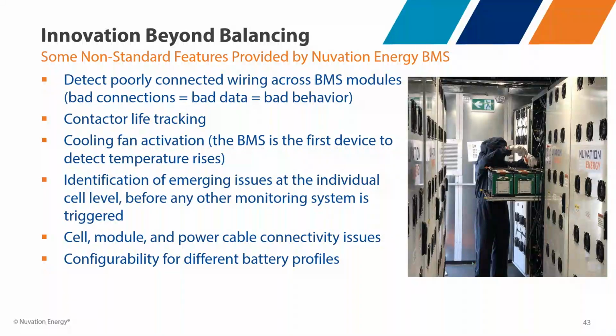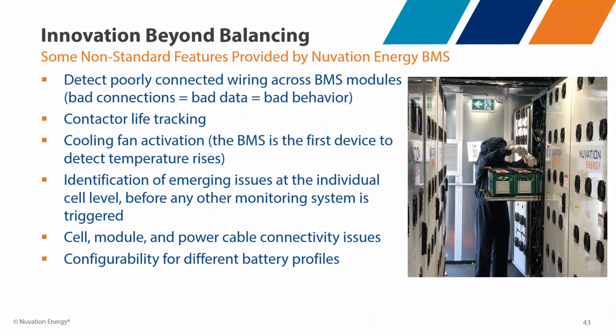We also have contactor life tracking. This is important to make sure that we stay within the lifespan of contactors. Contactors do have a finite life of a number of times that they can open, and it actually bins it out into different amounts of current. At very low currents, contactors have thousands of cycles that they can open and close. As you get to higher currents, you can do maybe 100. As you get into a higher bucket, it's maybe 10. And then at the max current of the contactor, you can get only a couple of openings. And so the BMS keeps track of this.